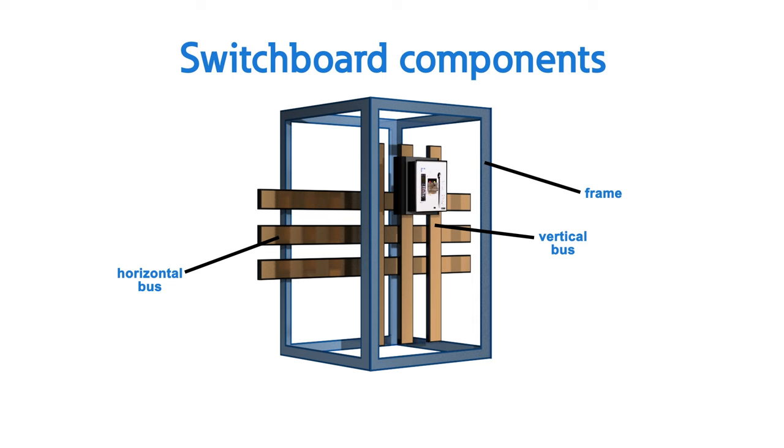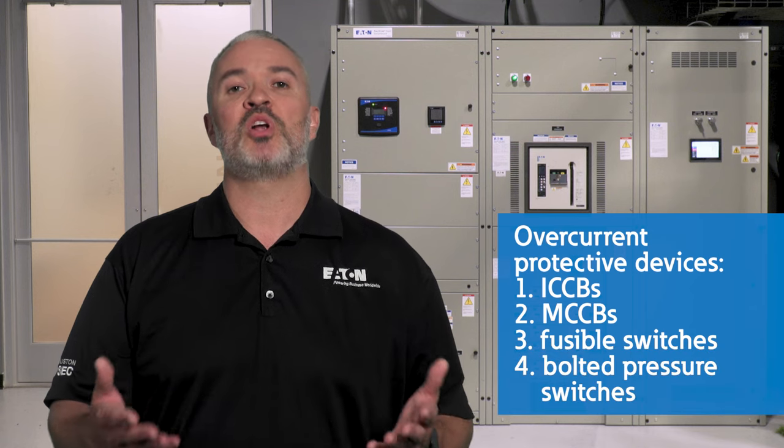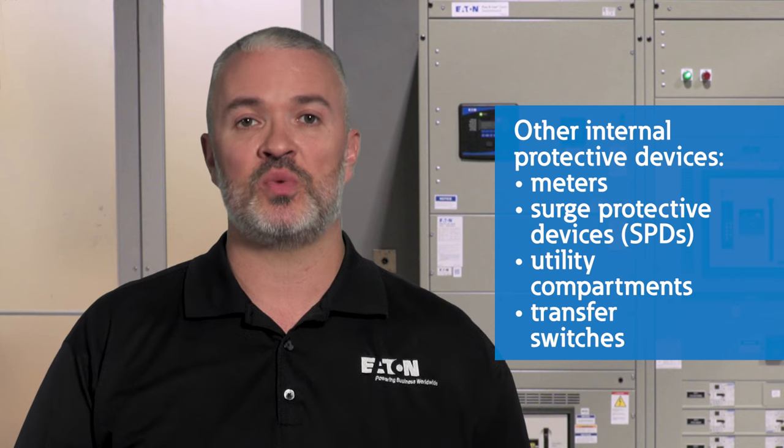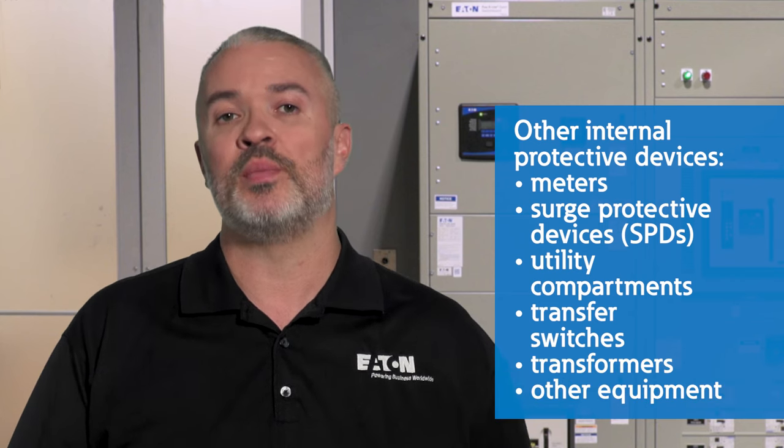The switchboard enclosure houses a number of critical components. Overcurrent protective devices are mounted to the vertical bus bars from the front of the unit. Four common types are insulated case circuit breakers, molded case circuit breakers, fusible switches, and bolted pressure switches. Other protective devices used in the switchboard interior may include meters, surge protective devices or SPDs, utility compartments, transfer switches, transformers, and other equipment.